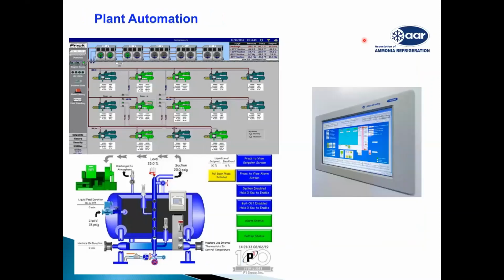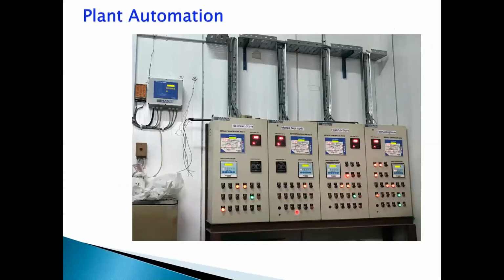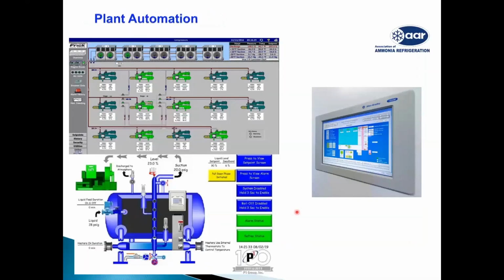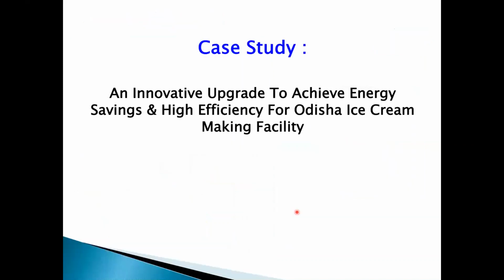Or we can have a centralized PLC system for a bigger plant, which will show you the complete plant in the system, and you can have everything covered. So all this is possible. The myth that an ammonia plant cannot be automated gets totally eliminated. It can be automated using discrete components, it can be automated using PLC systems, and you can have an operator-less plant.